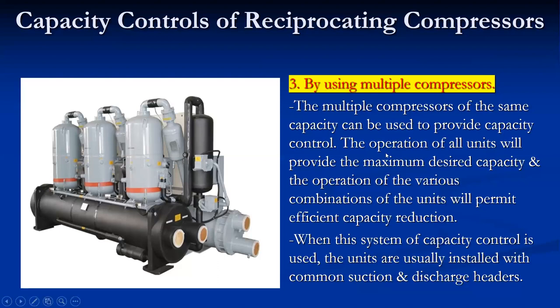Multiple compressors of the same capacity can provide capacity control. The operation of all units provides maximum desired capacity, while various combinations permit efficient capacity reduction. These units are usually installed with common suction and discharge headers. A typical layout includes compressors, oil separators, and accumulators. By shutting off a particular compressor, capacity can be varied — this is the third simplest method of controlling capacity in a reciprocating compressor.